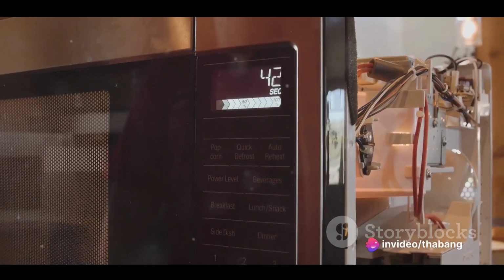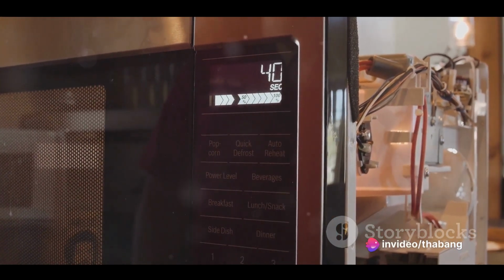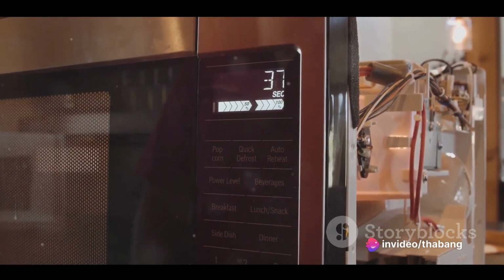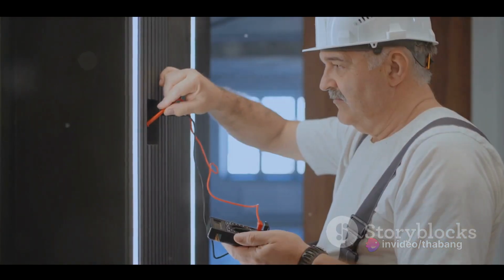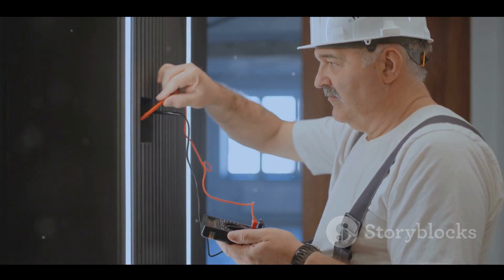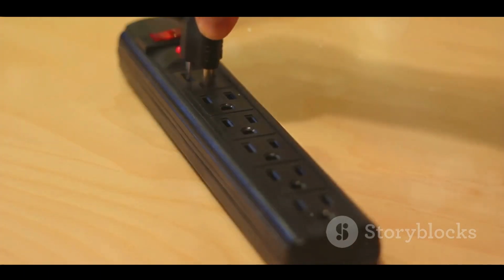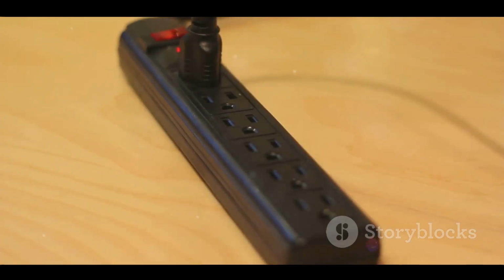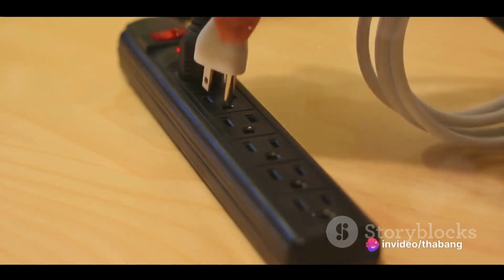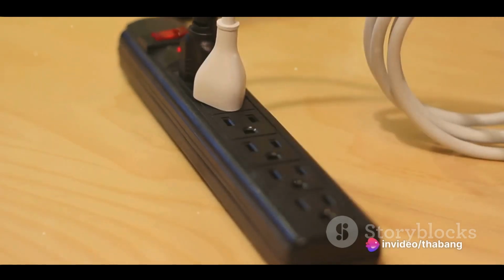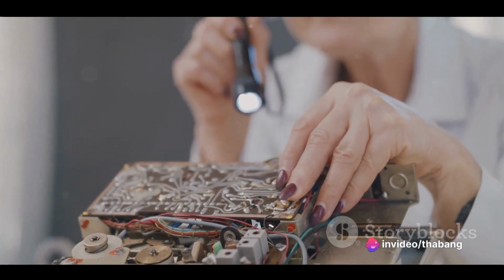Next, check which appliances are off, these are the ones supplied by the tripping breaker. Unplug these appliances and switch on the tripping breaker. Now plug the appliances back in one at a time and observe. The appliance that causes the earth leakage to trip is the one causing the problem. And just like that, you've identified the culprit.